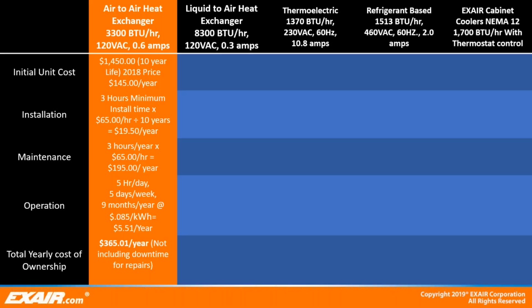So the upfront purchase price of this air-to-air heat exchanger is around $1,450. Spreading that cost over the manufacturer's expected service life of 10 years, we come up with a $145 cost per year. Using 3 hours as the minimum to install and a service rate of $65 an hour, spreading that over the manufacturer's expected service lifetime of 10 years, we come up with $19.50 per year. Using 3 hours as the minimum for yearly maintenance and a service rate of $65 an hour, we have a yearly cost of $195 for maintenance.